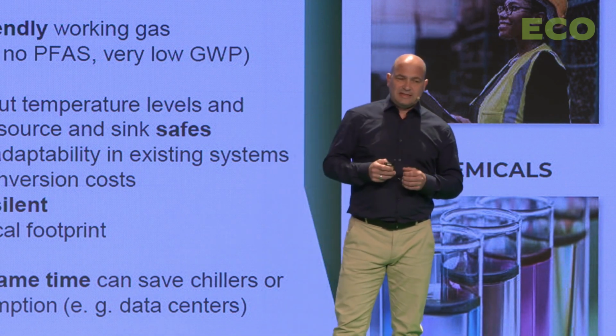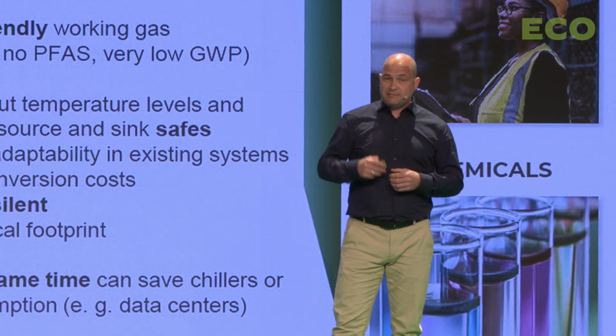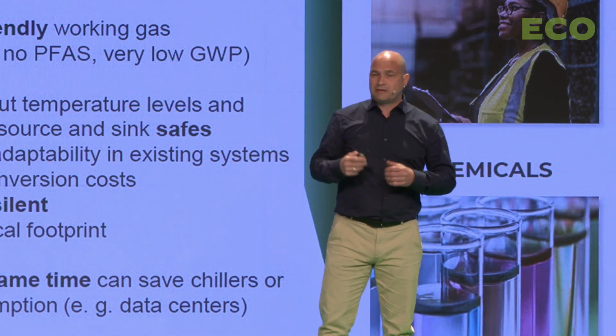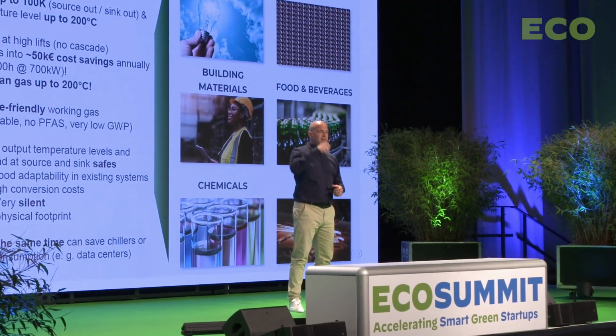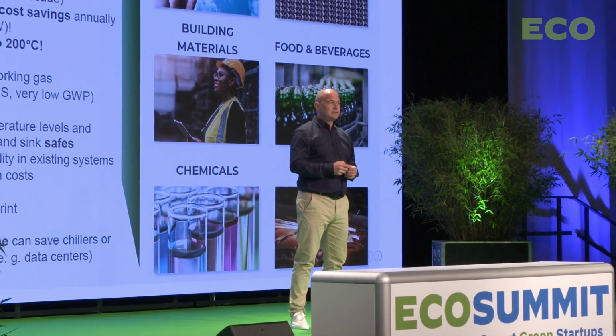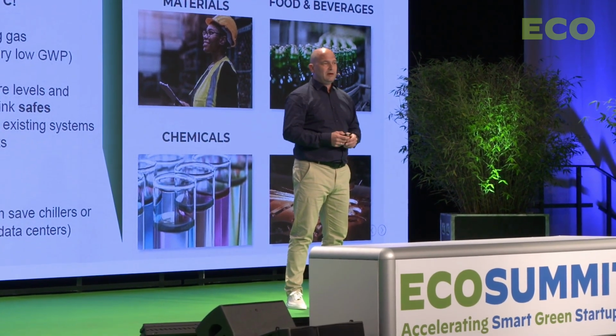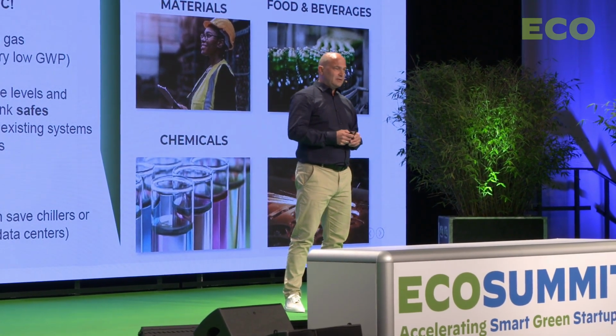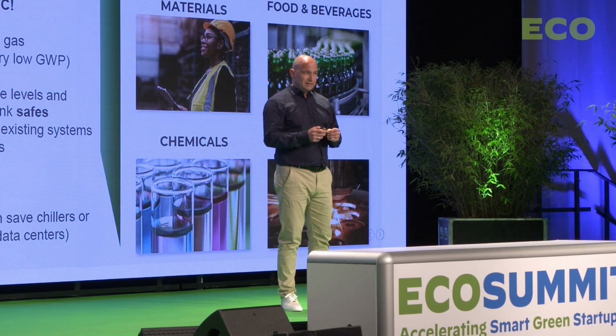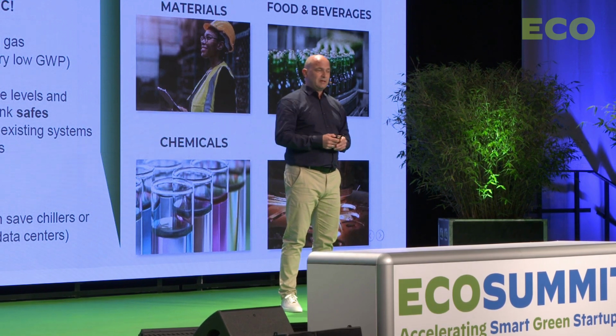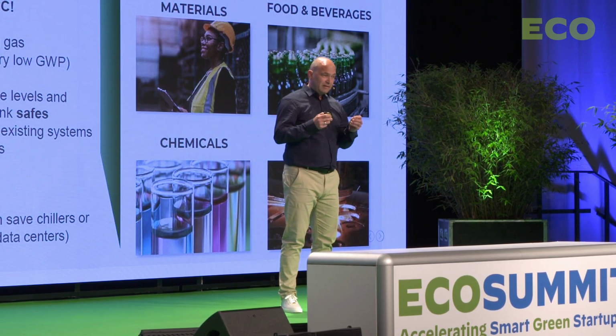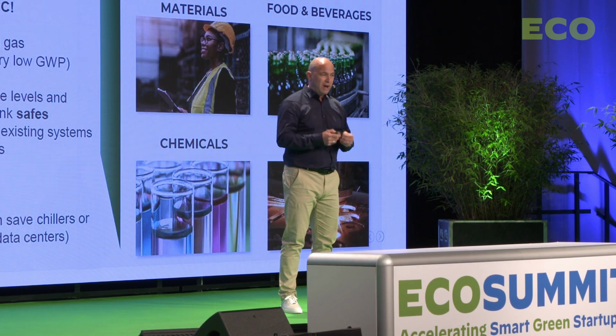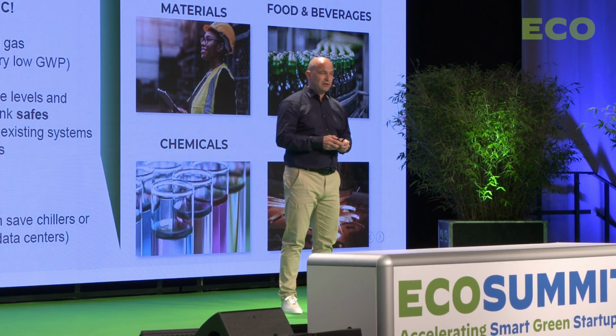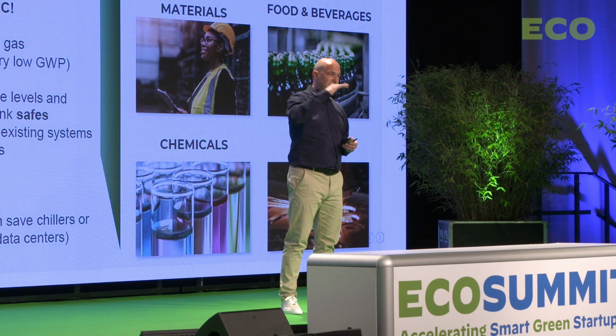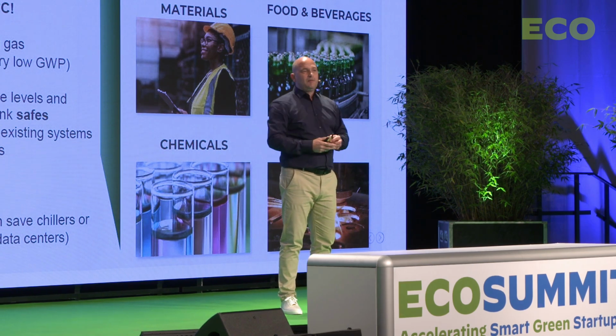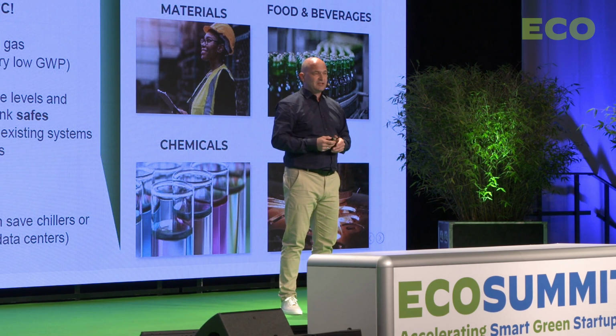Fourth, it's a very flexible system because we can vary and control the turning speed, and thus the lift, to cope with different input and output temperatures. Last but not least, it's very silent because it's a constant turning process. And we can cool better than a conventional heat pump because we take off heat in a glide rather than in an evaporation, so the system doesn't make a phase shift.